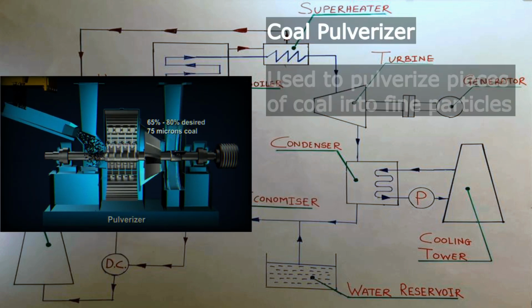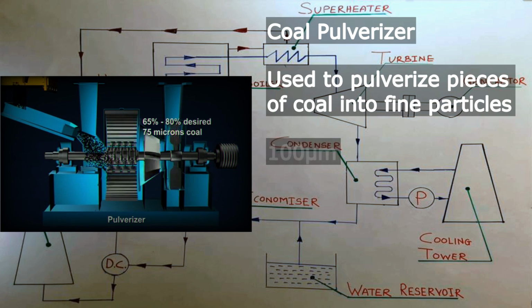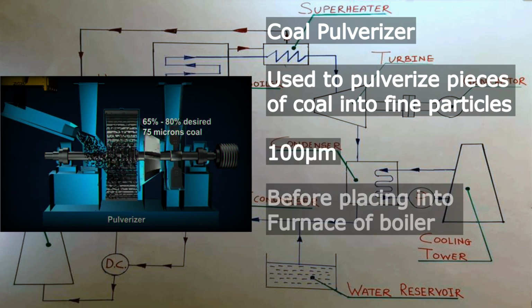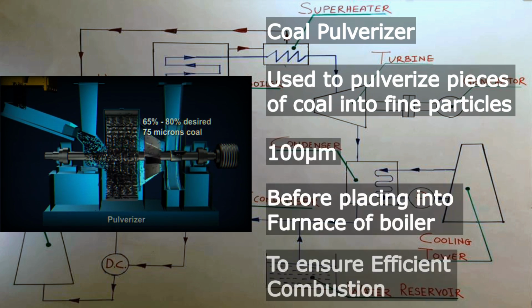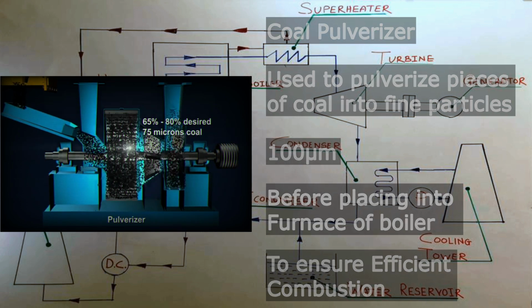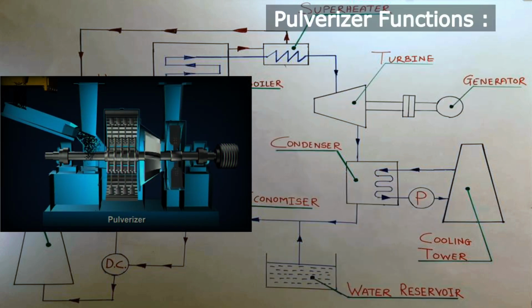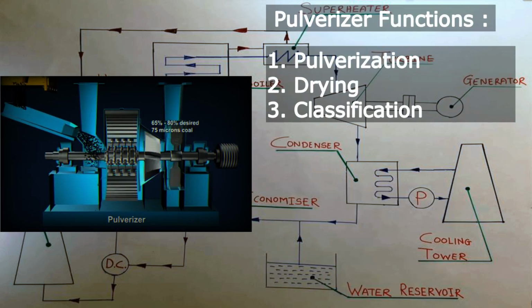So pulverizers, or you can say the coal pulverizer, are used to pulverize pieces of coal into fine particles that is approximately equal to 100 micrometer before placing into a combustion chamber, that is furnace of a boiler, to ensure efficient combustion. Pulverizers have three functions. First one is pulverization, second one is drying, and third one is classification.